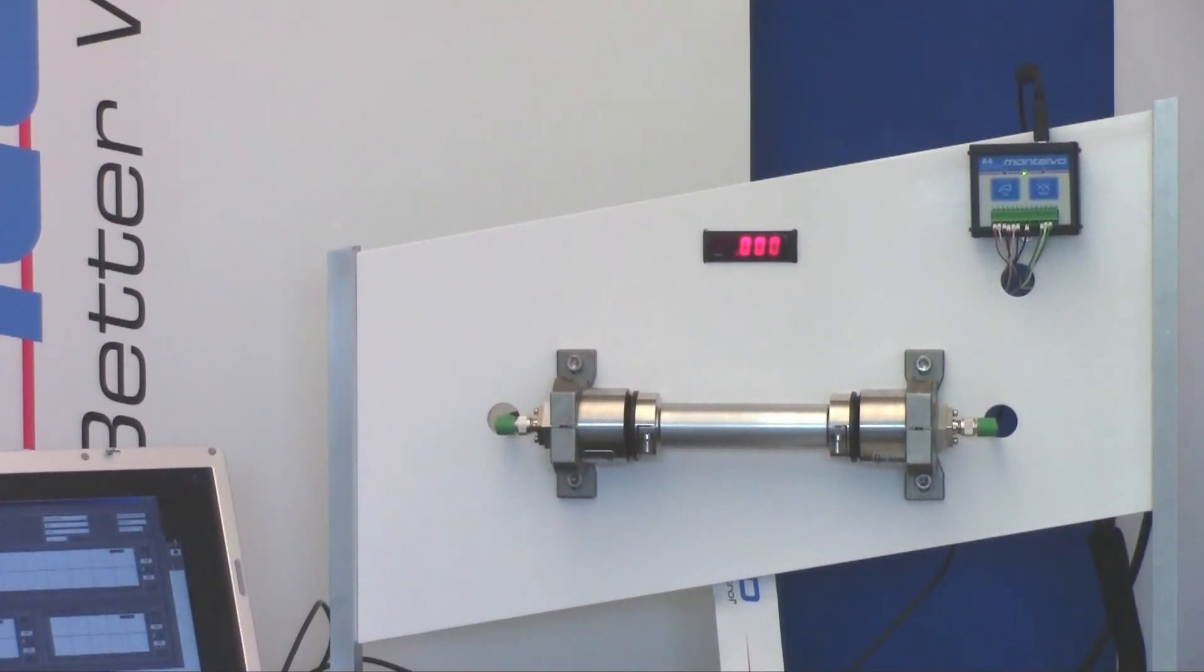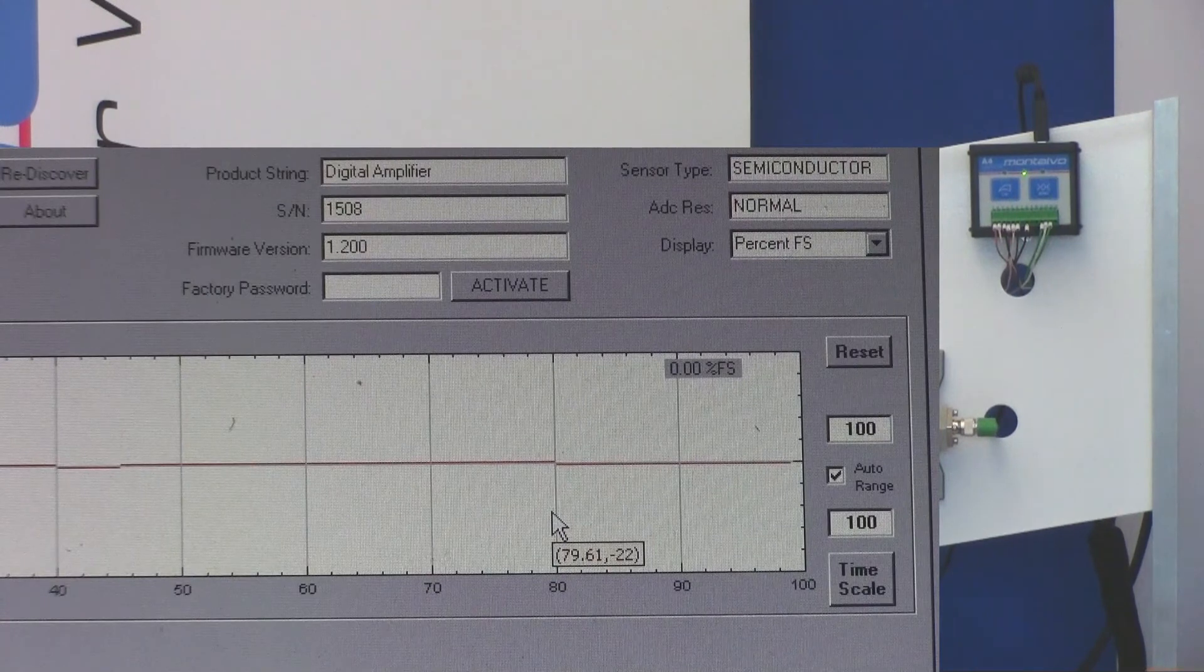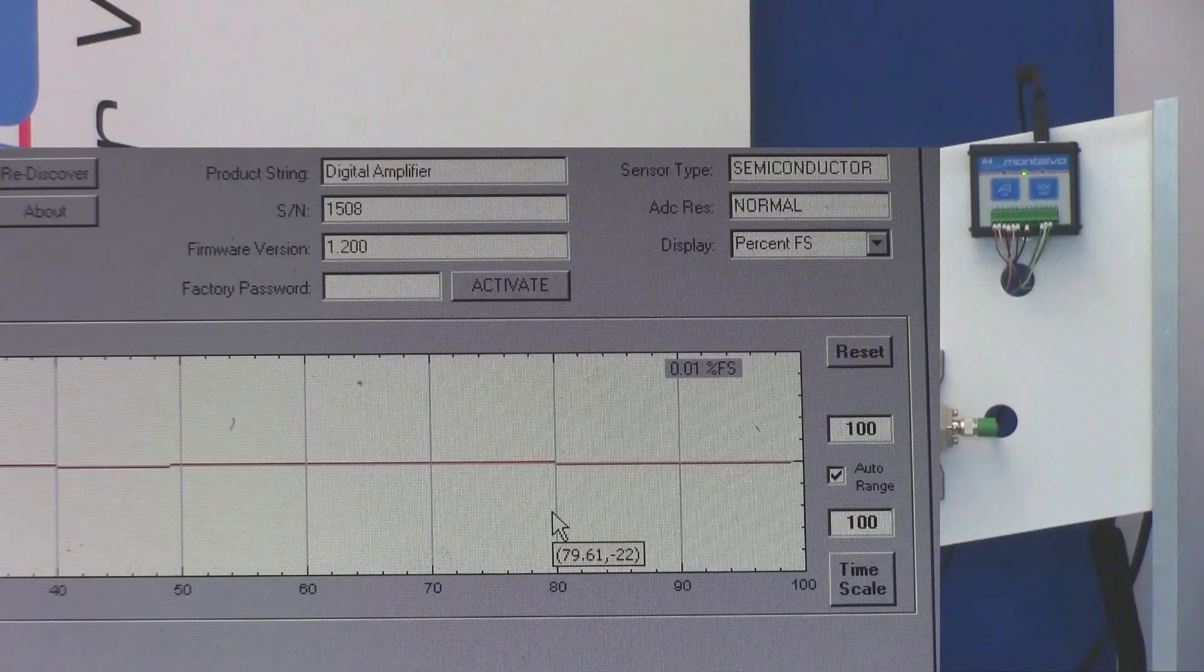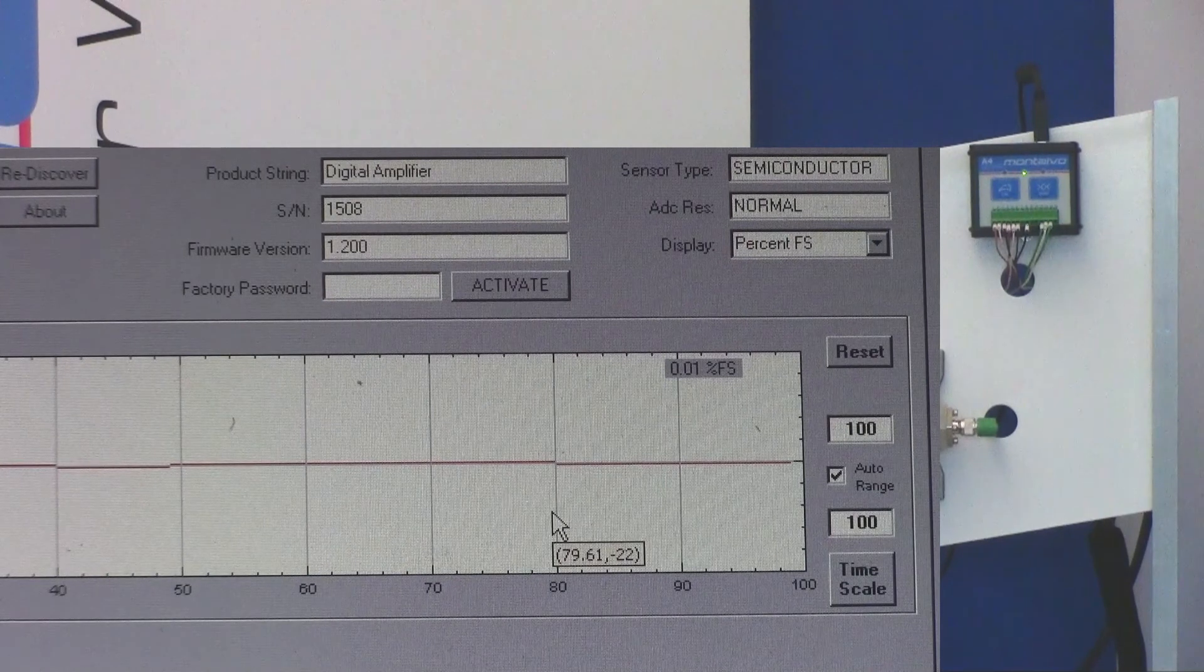So, let's rewind the data and take a look. As you can see, the load cells are reading 0.01% of their full scale. Only five grams and the load cells are registering a change in tension.